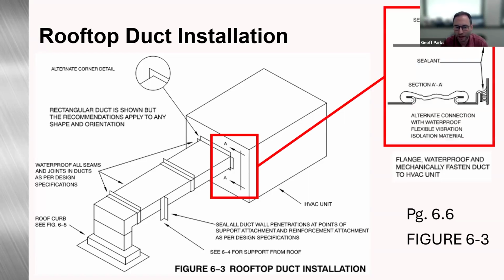And then kind of zooming in here on our unit connection, this can either be a solid connection, based on, whoops, sorry, I got a picture of myself covering this section AA. Again, it's either a solid connection, if the HVAC unit is internally isolated or the duct's internally isolated, or you have your flexible connector somewhere else in that line. Or, in many cases, you're going to tie into that unit directly with a flexible connection for vibration isolation.